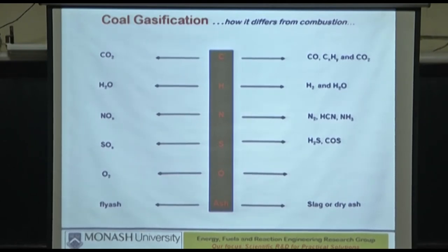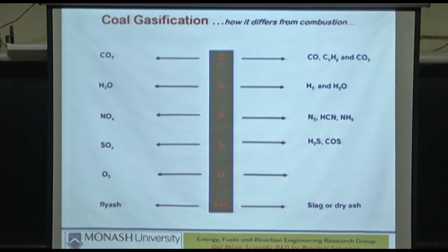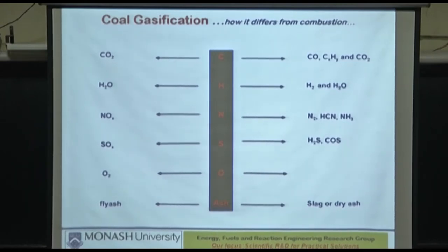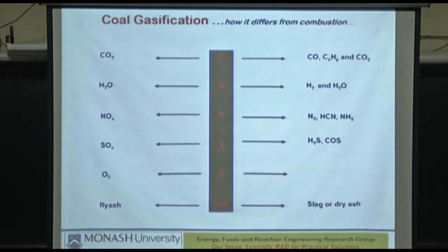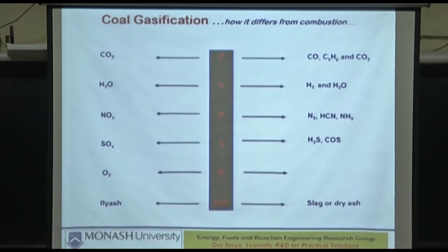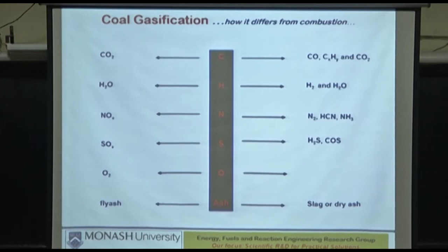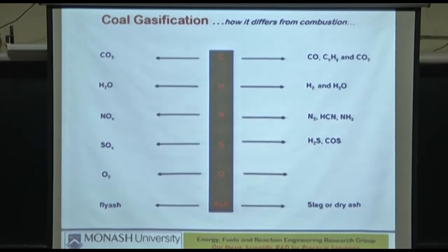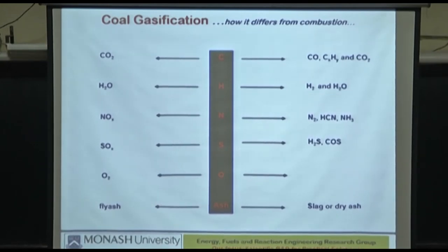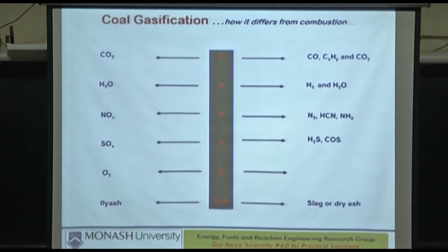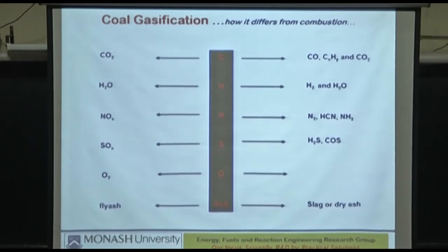So in the coal-fired boilers, the burners are designed in such a way that nitrogen in the air doesn't come in close proximity to the oxygen in the coal. So the air is actually staged so that there is not a large amount of nitrogen at every level. There are special burner designs. In fact, it's a specialized area. It's called low NOx burners, which deliberately suppresses the temperatures near the burner where NOx can form to the minimum quantity, but you still cannot avoid it.